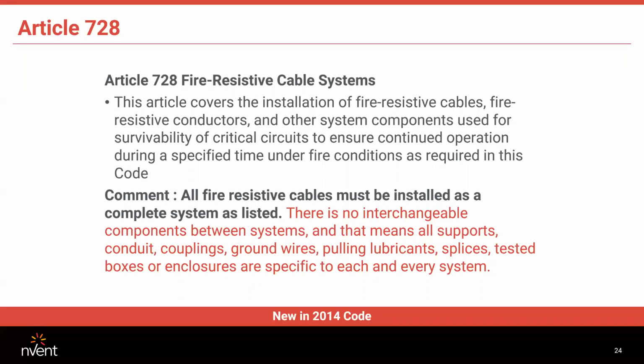Okay, and as I mentioned also, there is Article 728 in the NEC, and that basically covers all the requirements that fire-rated cables must comply with before they are used. And they have something interesting there, that there are no interchangeable components between systems allowed. So basically what they're saying is whatever the cable is supported to has to be tested with that cable. So anything used with that system has to have been tested, and you can't do a hodgepodge of systems. They have to be tested together.